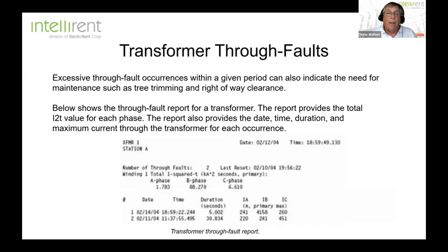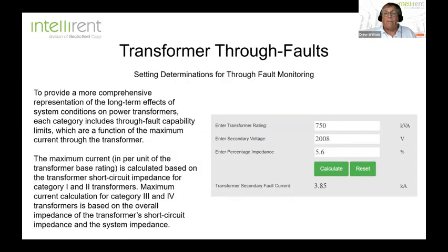You can see here in this sample report, and of course, this is the relay software giving you this data, and it's a little bit fuzzy, but you'll see that it shows you the three phases of where they may have occurred, the magnitude in terms of how much current, and then the date and time. Because what's important to know is that one single through fault, while it may not damage the transformer, if they're reoccurring continuously, puts continuous stress.